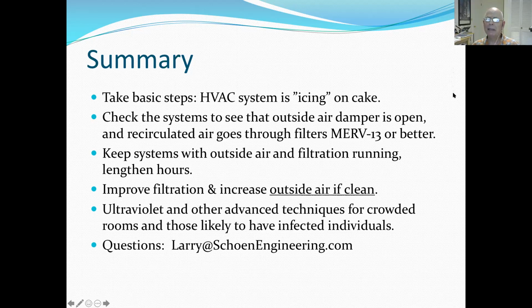How do you define a decent HVAC system? In terms of, as I said, outdoor air dilution ventilation per person. I gave some numbers there. The current codes require 8 or 10 CFM, depending on the density in the room. 15 or 20 CFM per person is even better. And the Europeans say even higher than that is even better. If I were running a facility and I wanted to reduce my risk, I would say at least 15 CFM per person. I would try to go higher.